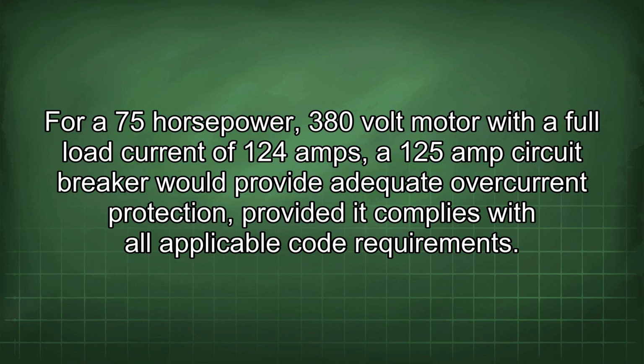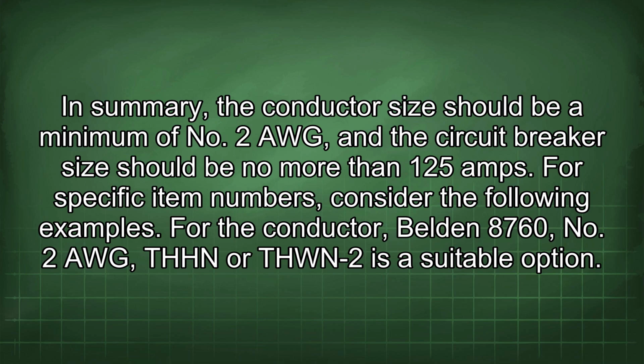For a 75 horsepower, 380 volt motor with a full load current of 124 amps, a 125 amp circuit breaker would provide adequate overcurrent protection, provided it complies with all applicable code requirements. In summary, the conductor size should be a minimum of No. 2 AWG, and the circuit breaker size should be no more than 125 amps. For specific item numbers, consider the following examples.